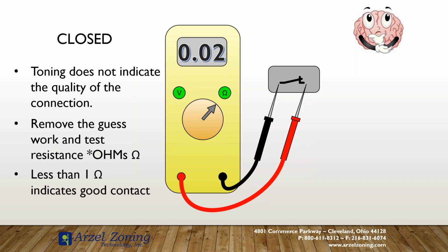So when we're testing for resistance, we want to look and see if we have less than 1 ohm of resistance. If we have that, we know we have a good contact. So if we have an issue with our furnace not working and we've tested our resistance on a specific circuit, we read less than 1 ohm, we know that our problem is now somewhere else because that contact is proven. It's verified good.